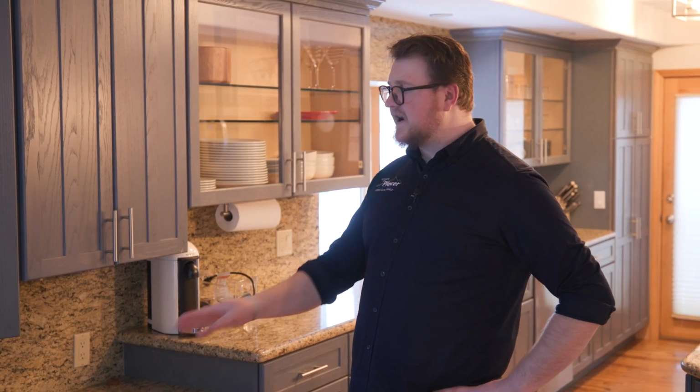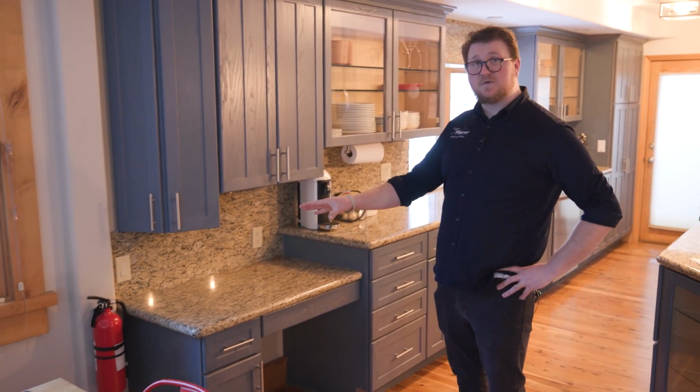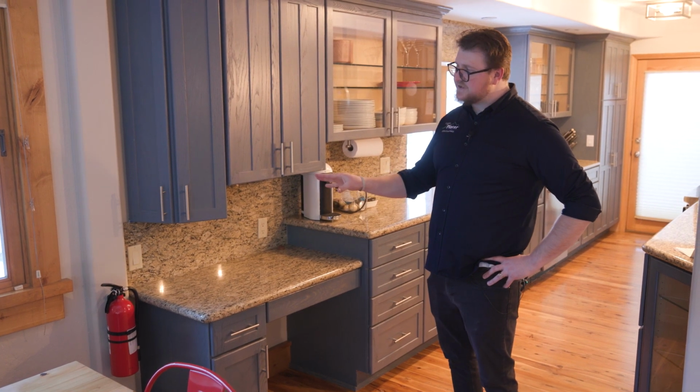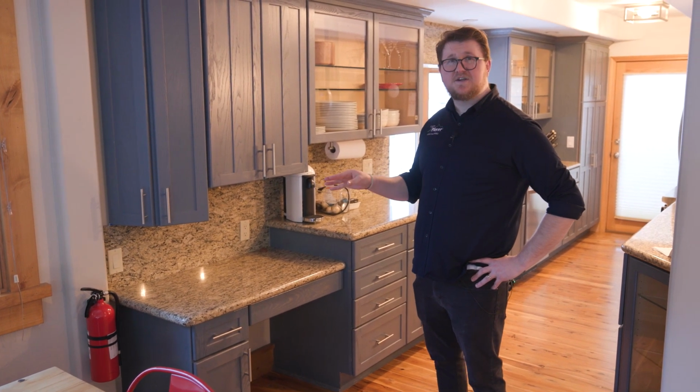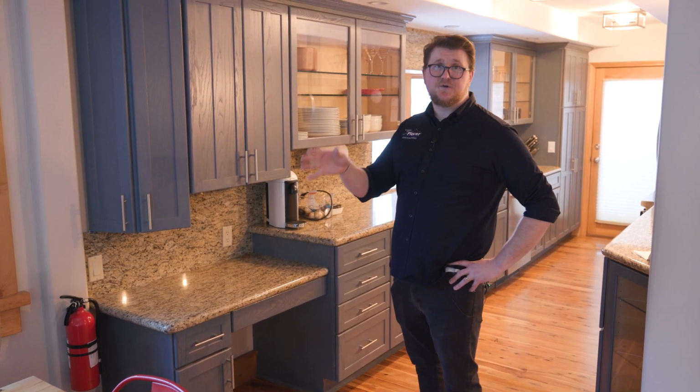In addition to a fire extinguisher being required on every level of the STR, I want to draw attention to the fire extinguishers on the level a kitchen is located. Now for these extinguishers, they need to be within 10 feet of the kitchen, and when in the kitchen, there needs to be a clear line of sight to that extinguisher.